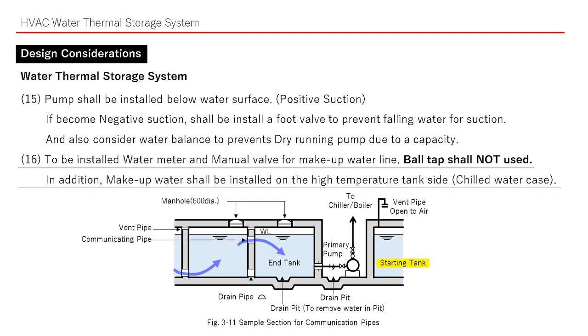A water meter and manual valve shall be installed for the makeup water line. A ball tap shall not be used. In addition, the makeup water inlet shall be installed on the high temperature tank side — meaning, for chilled water, consider the makeup water in the starting tank.